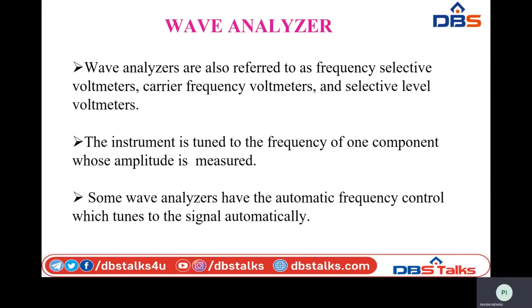Some wave analyzers have automatic frequency control, which tunes the signal automatically. So we have 2 types of wave analyzers which operate with a particular frequency. Whenever the capacitor or resistance is varied, it gets adjusted. Otherwise, we have Q factor filters and active filters, whose quality factor is better. Those kinds of analyzers are automatically adjusted to a particular frequency with the help of tunable oscillators present in them. That is why some analyzers have automatic frequency control, unlike the basic wave analyzers.